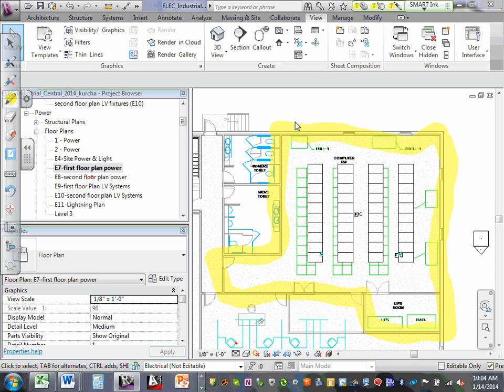Okay, standard stock-type smoke detectors are rated for 900 square foot coverage. Let's say, for the sake of the project, the air changes per hour in this room would require you to space your detectors on 450 square feet. So what's the square root of 450? Anybody got a calculator? Okay, 21.2. So let's say 21 feet is going to be your spacing for your subfloor smoke detectors. For that matter, it might be your spacing for your detectors on the ceiling as well.